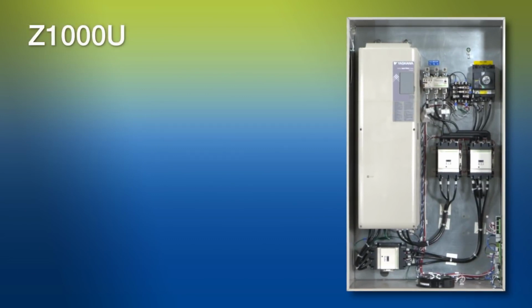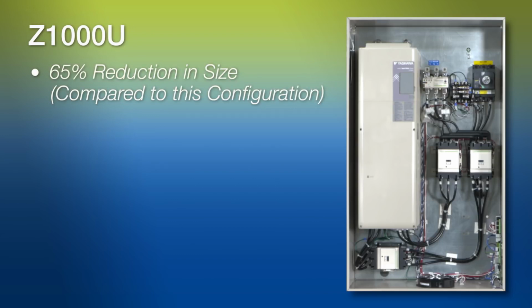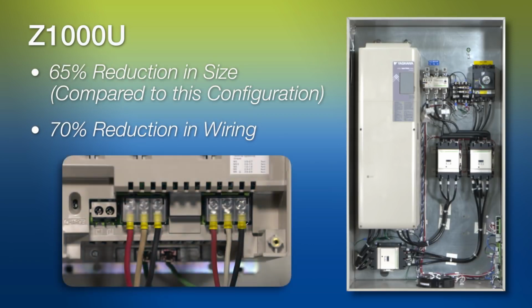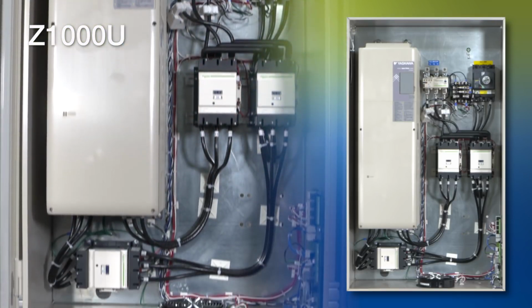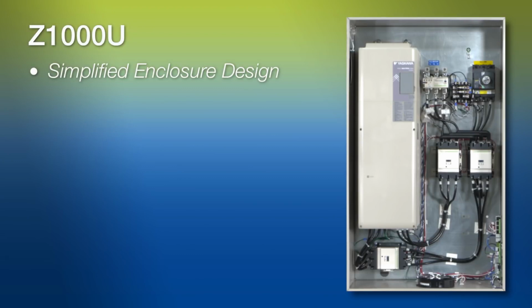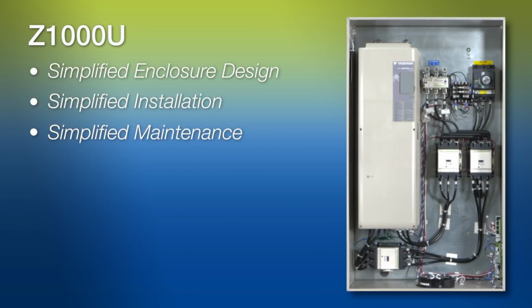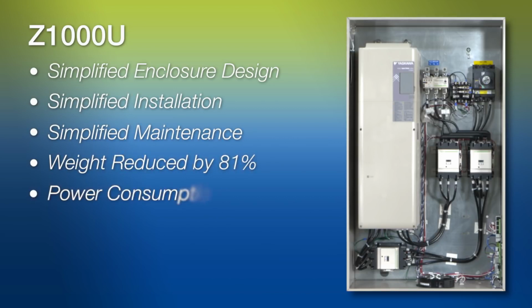The Z1000U has a 65% size reduction compared to this configuration. Wiring is reduced 70%, from 20 wires down to 6. That's just 3 in and 3 out. Eliminating external devices also eliminates the necessary wiring and space required for those devices, simplifying the enclosure design, installation, and maintenance. Weight is reduced by 81%, and power consumption is reduced by 19%, all while maintaining that all-important IEEE 519 guideline.